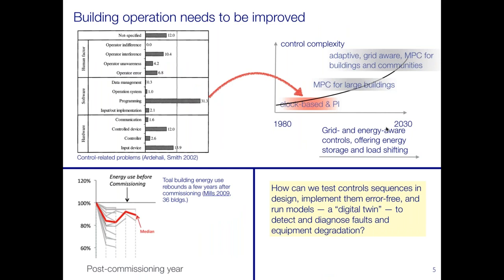Looking at today's control-related problems from a survey conducted a bit more than 10 years ago, it pointed out that the most frequent control-related problems are due to programming errors. That's a bit disconcerting, because these systems are typically simple clock-based controllers with a time schedule and a proportional-integral loop that tracks the set point.